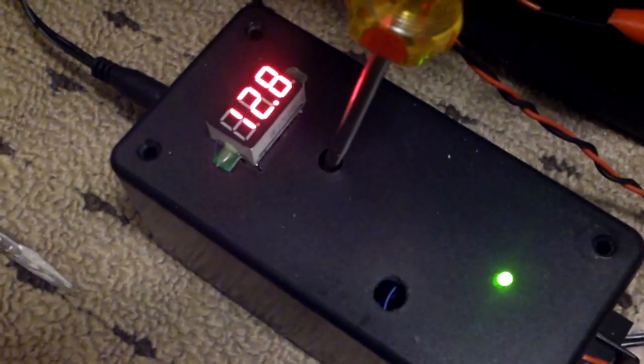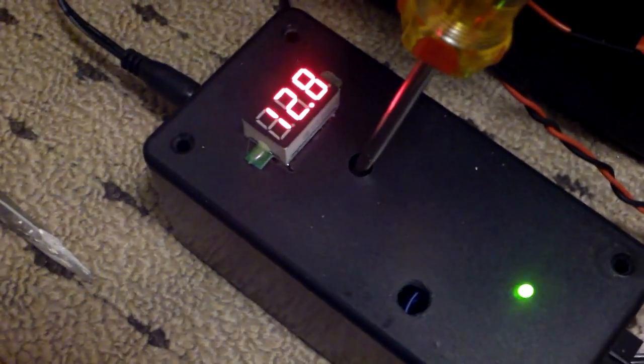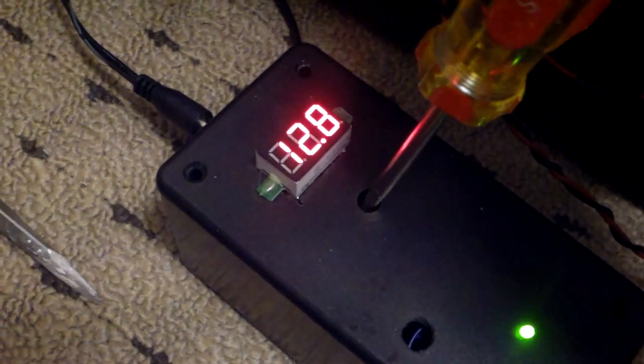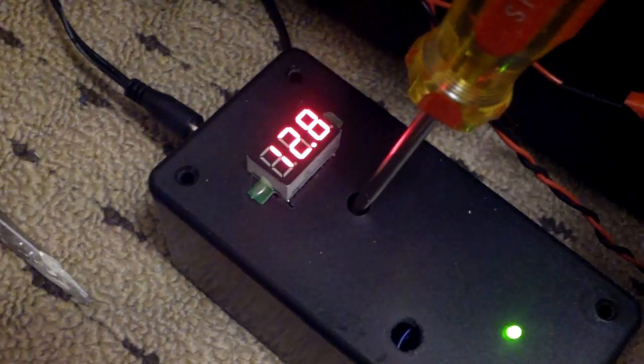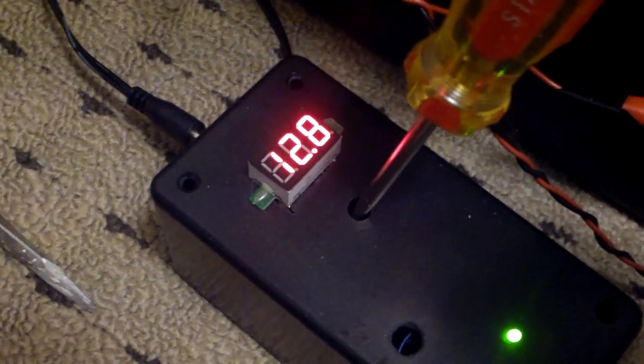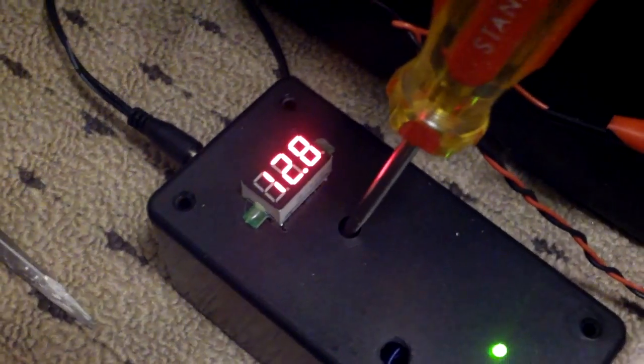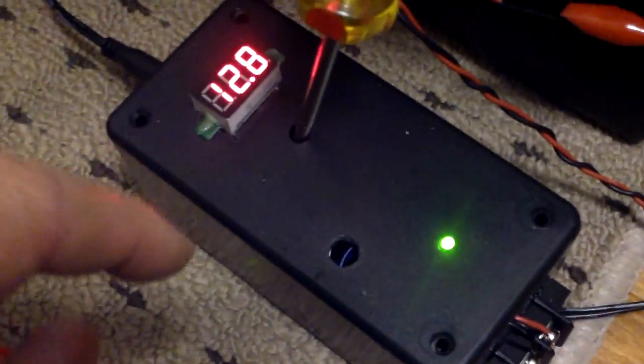But I don't really want it to cut in at such a higher voltage, so I'm going to set it so it would charge between 11.5 to 12.5 volts. What voltage it starts to cut in sometimes depends on the voltage of the battery.